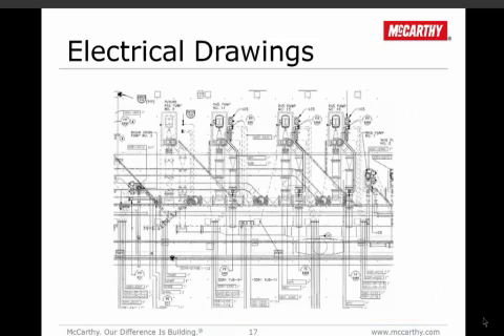In this area we're going to get into talking about the coordination of electrical, mechanical, and instrumentation drawings. In pre-construction, while these plans are being developed, we can help ensure that there's proper coordination, that equipment is tagged and identified on all the drawings so that we are able to properly have the proper power, startup, and testing of that equipment. Electrical drawings will show flow meters. On there, we have to verify that we have the right conduit for power as well as control, and then it reflects the actual equipment that's being furnished. We have local control stations that we will need to verify startup of and verify remote control from SCADA.